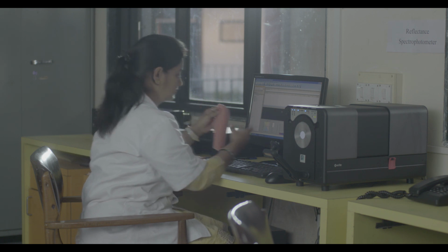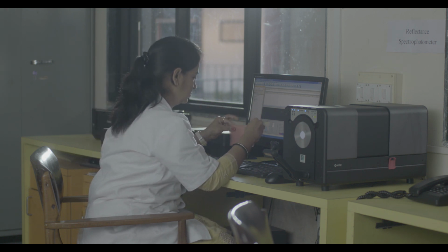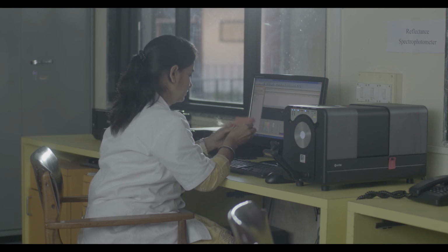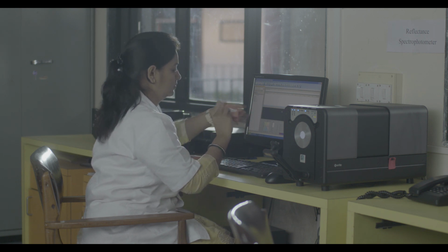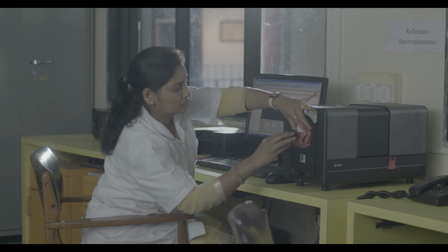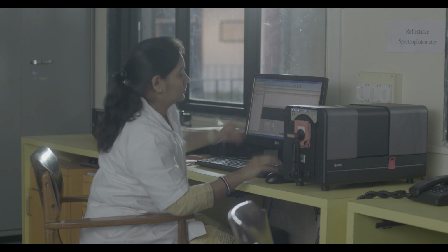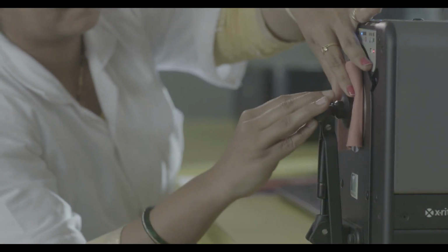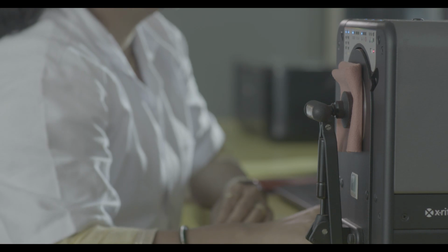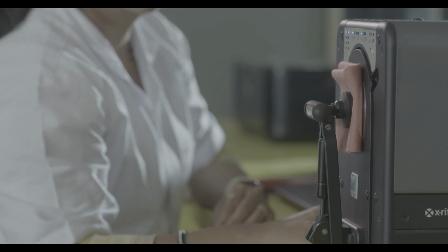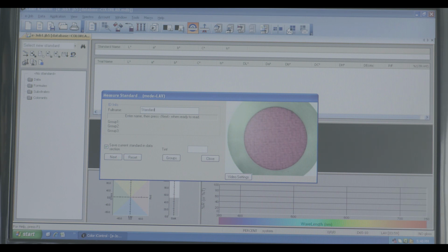Color difference measurement. We can measure color difference between the sample and batch material. For this, first take a standard sample and fold it. Open the sample arm on the spectrophotometer to the fully open position. Present the sample at the viewport and slowly close the sample arm. The spring on the sample arm is dampened to prevent the arm from closing with too much force and possibly damaging the sample. Use your computer screen or the drop-down door to view the sample and adjust the sample measurement targeting area. Select Measure Standard from Software Interface.